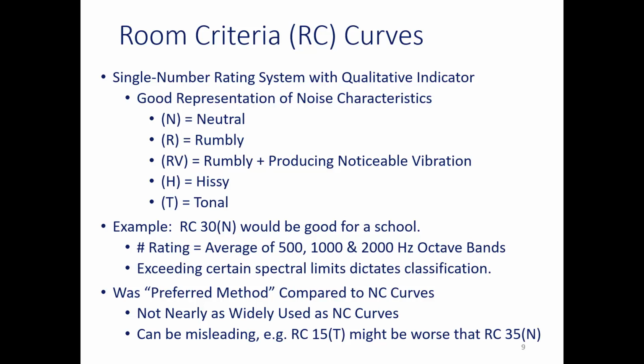So this was the preferred method compared to NC curves, and there's a newer version of this, which is now the preferred method, but for a long time this one was the preferred method. I don't want to say this in the wrong way, but what I wanted to say was that it never really took off very much. I don't know if that's the most accurate thing, but maybe a better way of saying it is that most engineers, most consultants, and most manufacturers of equipment always use the NC. They never really switched over to the RC.